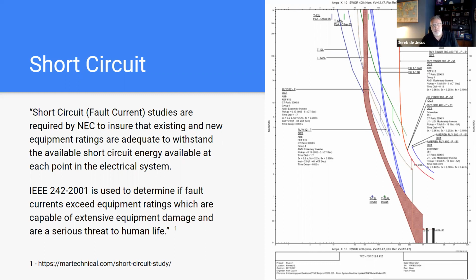A lot of times, using a BIM Revit model, they can pull the preliminary lengths so that the vendor can start to develop that study early. And this plays into the point of having a preliminary study at a factory or at an integrator, such that you can get some of that information. If the project has a BIM and Revit model, they can start to gather what those lengths are, within a few feet. And then as the EC takes over that model and starts to develop their bill of material for cable purchasing, those numbers get refined and validated. The ETAP model or the SKM model is then updated to reflect the actual available fault current at those devices.